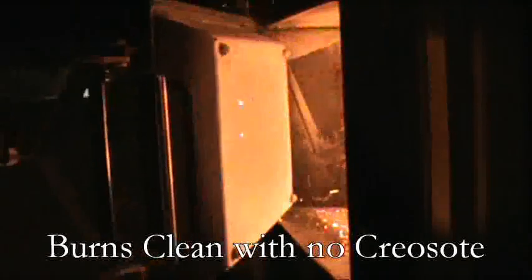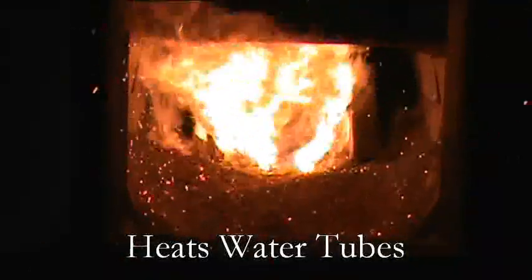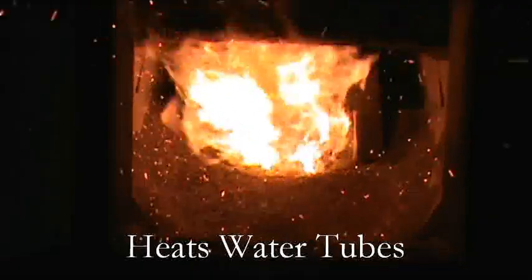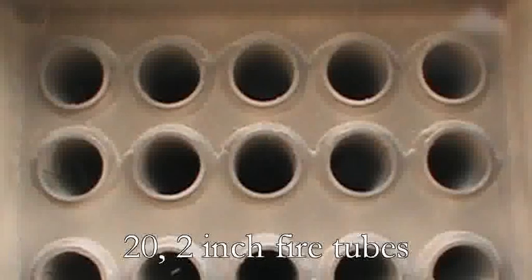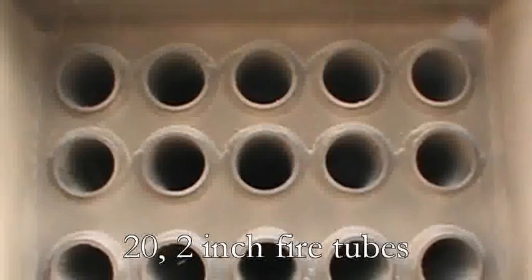The boiler is designed to be very efficient. The fire is completely surrounded with water. There are three water tubes located just above the fire for maximum heat extraction, and a wet baffle in the back of the fire pot that keeps heat in the fire pot longer. The heat is then directed through twenty, two inch fire tubes which are surrounded with water.